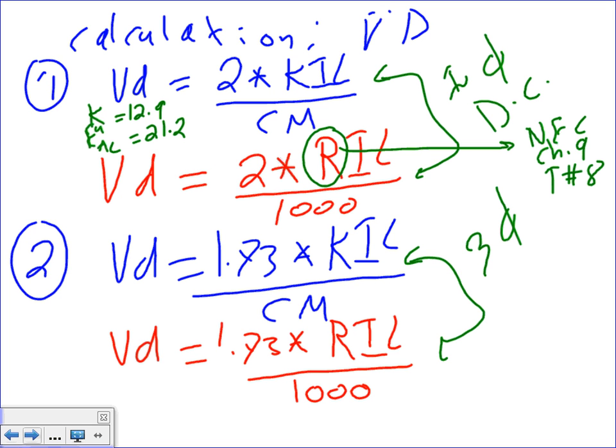Okay, so we established the criteria. We use R for DC, guys, for the most part. Later on, we can start using Z, the impedance, which is table number 9. So can you guys write also table number 9. Table number 8 and table number 9 is where you get the R, which we're going to change into Z later on. Yes, sir.